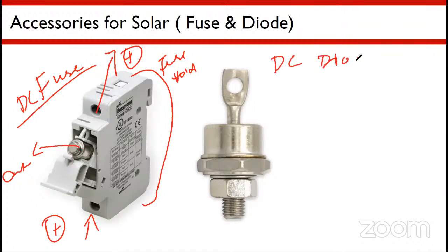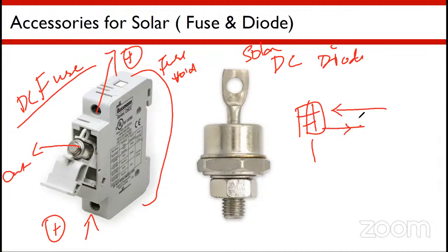This diode is mainly used to always allow current to flow from the PV module to the inverter, not from the inverter to the PV module, because a diode is a unidirectional device - it allows current flow only in one direction. It's designed so the DCDB box will only take supply from the array to the inverter, not in reverse. The diode is implemented to ensure this condition.